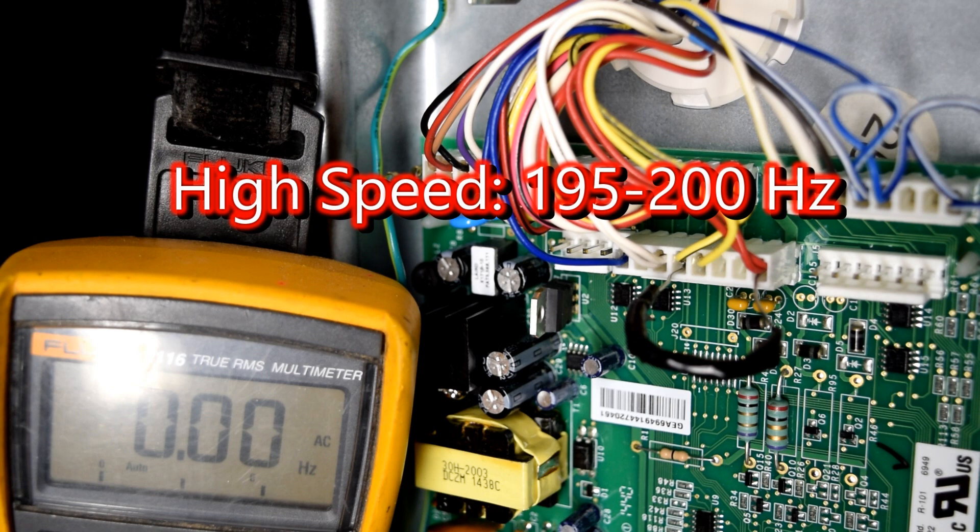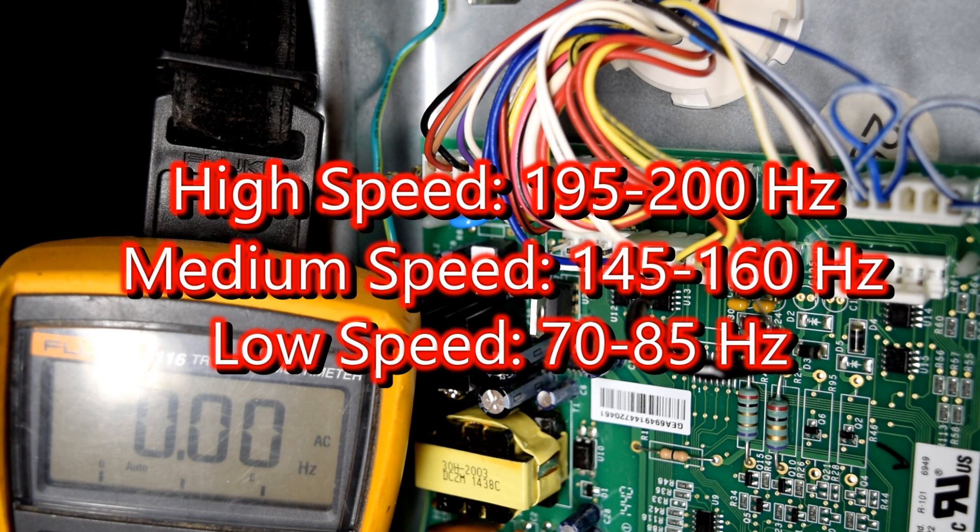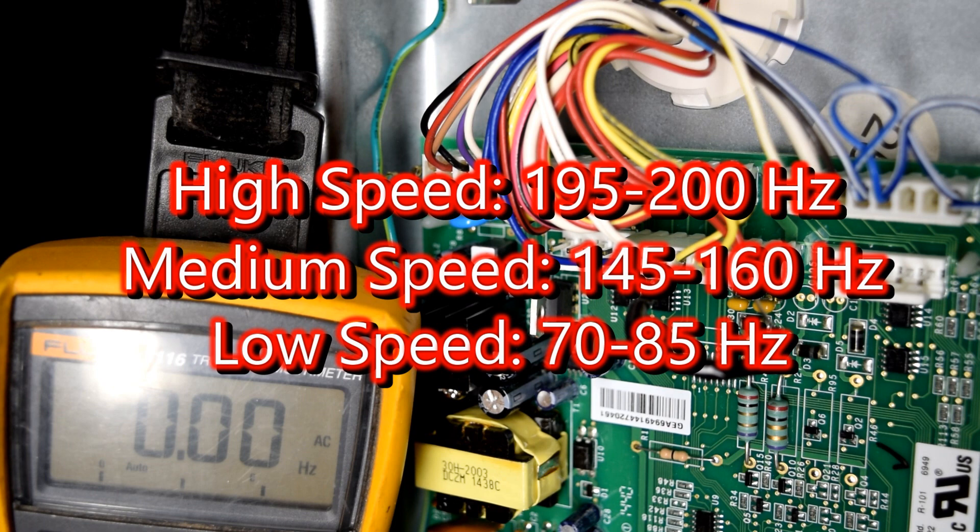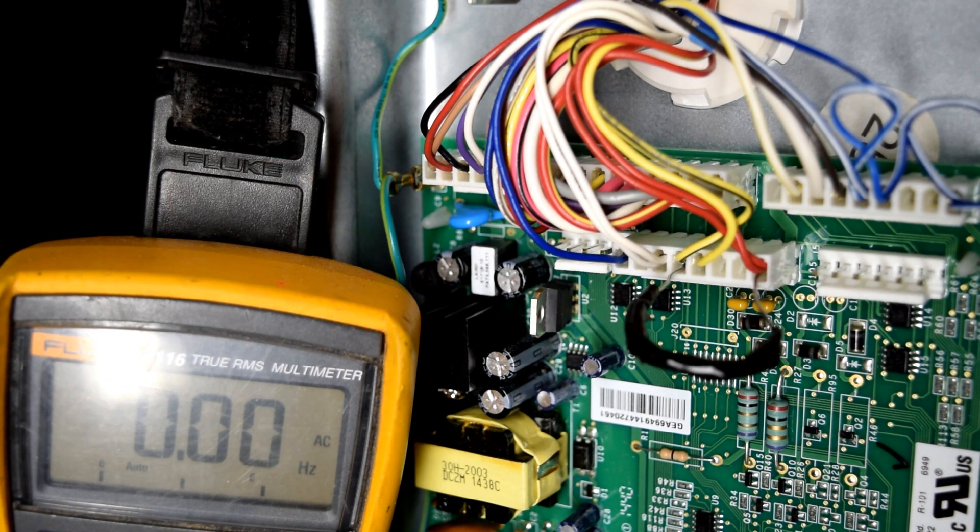Medium speed is 145 to 160 Hertz. And then low speed is 70 to 85 Hertz. And based on that Hertz response from the tachometer, the board then knows whether it should speed up or slow down.